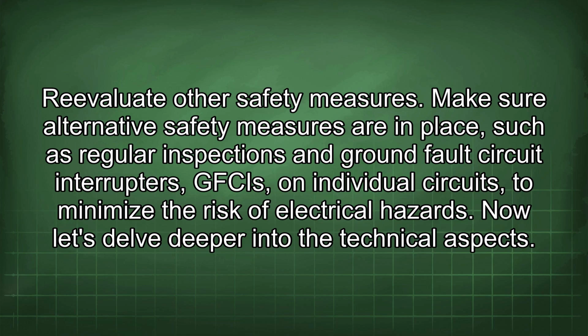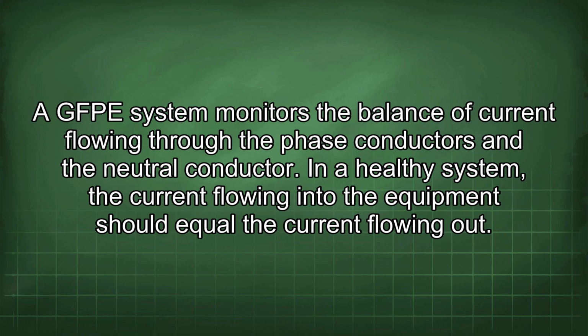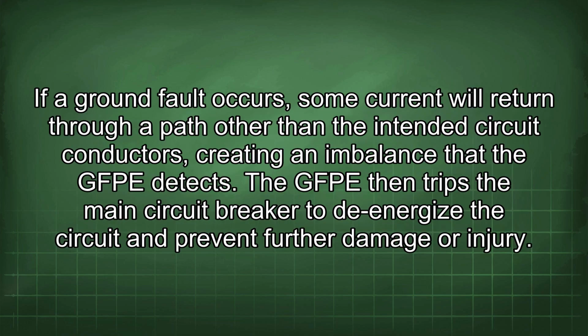Now let's delve deeper into the technical aspects. A GFPE system monitors the balance of current flowing through the phase conductors and the neutral conductor. In a healthy system, the current flowing into the equipment should equal the current flowing out. If a ground fault occurs, some current will return through a path other than the intended circuit conductors, creating an imbalance that the GFPE detects. The GFPE then trips the main circuit breaker to de-energize the circuit and prevent further damage or injury.